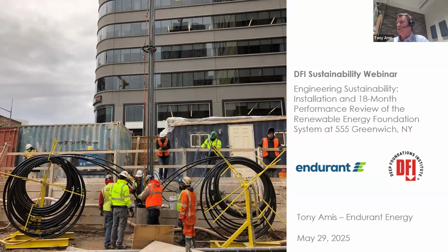Thanks Matt, and thanks Cerys, for a fabulous example of the added value that can be had by simply putting geothermal loops into piles. I've been saying it for probably the last 25 years, so it's really good to hear it coming from other people. But ground source heat pumps versus air source heat pumps is always going to be a battle. The cost of the unit itself is very similar between the two. The big additional cost of a ground source heat pump is putting the geothermal loops into the ground, and on projects where you're putting in deep foundations, it just makes so much sense. Any project I see now with no geothermal loops going into the building, that's such an opportunity being missed, it seems to me.